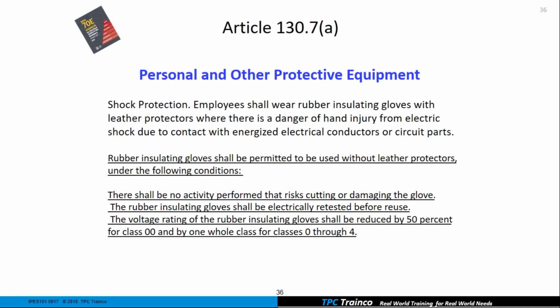So I could still work around 480 with that class 0 glove, and I wouldn't have to put a leather protector on there, as long as it wasn't going to risk the chance of it getting cut or damaged, whatever I was doing. A good example would be if I had a large cabinet with multiple voltages in there, and maybe I had to protect myself to that higher voltage, but all I was really doing was going through the display of a variable frequency drive.